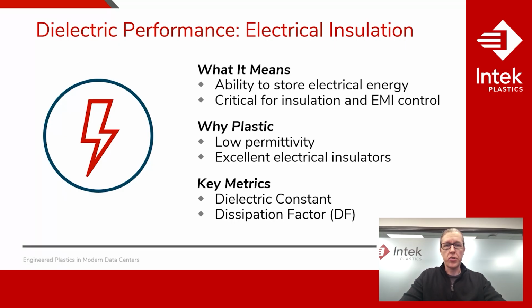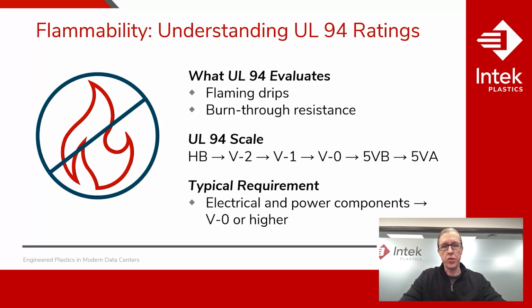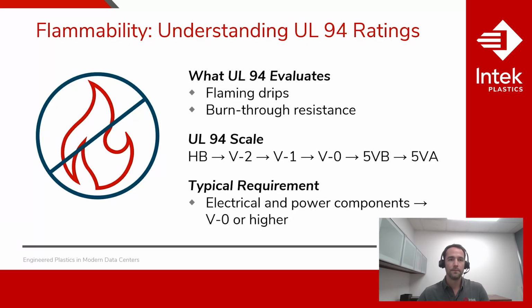Flammability. Let's talk a little bit about understanding UL 94 ratings. Levi, can you talk us through this one as well? I can take care of that one. So flammability testing for plastics is governed by a variety of standards, including ASTM and NFPA. But the one that's probably most familiar to people is UL 94. UL 94 evaluates the burning behavior of a material, and it looks at three primary criteria, those being how quickly or whether a material self-extinguishes, whether it produces flaming drips that ignite a cotton ball positioned below the test specimen, or whether the flame can burn through a material from one surface to another.